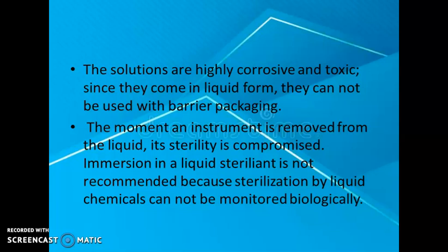And the solutions may sometimes be highly corrosive and toxic since they come in liquid form. They cannot be used with barrier packaging. The moment an instrument is removed from the liquid, its sterility is compromised. Immersion in a liquid sterilant is not recommended because sterilization by liquid chemicals cannot be monitored biologically. So it can't be monitored biologically using spore strips.